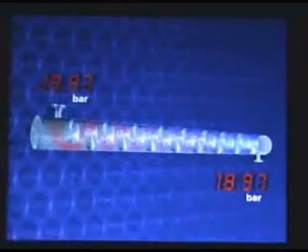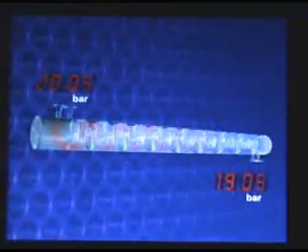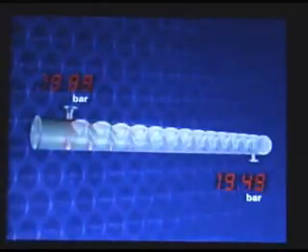By obstructing the flow with segmental baffles, a high fouling tendency occurs in the dead zones behind the baffles. Depending on the fluid, this shortens the run length significantly. The Helixchanger heat exchanger has no dead zones because of the smooth guidance of the flow, so the fouling is minimized and a long run length can be expected. Every shell and tube arrangement has a pressure drop, a great deal caused by the baffle arrangement. Compared to the conventional systems, the smooth guidance of the flow in the Helixchanger can improve the shell side pressure drop up to 50%.